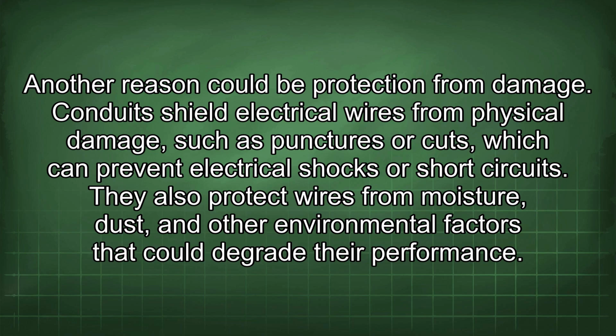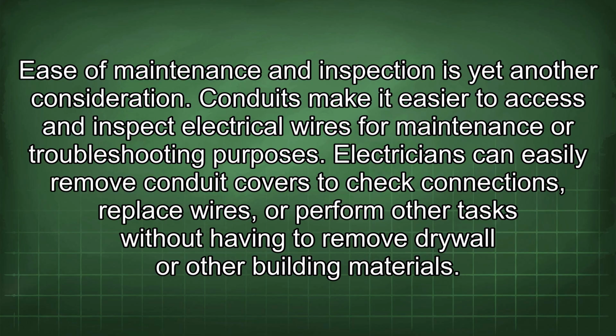Conduits shield electrical wires from physical damage such as punctures or cuts, which can prevent electrical shocks or short circuits. They also protect wires from moisture, dust, and other environmental factors that could degrade their performance. Ease of maintenance and inspection is yet another consideration. Conduits make it easier to access and inspect electrical wires for maintenance or troubleshooting purposes.